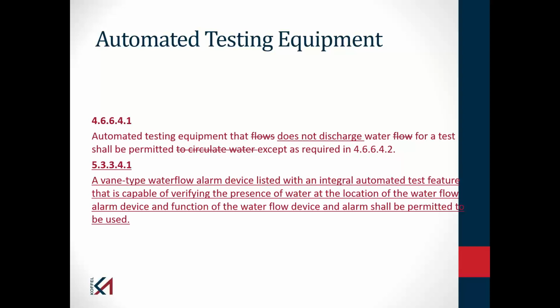So technology is advancing to the point that I can now get automated test equipment for certain components of my sprinkler system, one of which is a water flow alarm. So in the 2017 edition, we recognized that automated test water flow device, but we required it to flow water. A change in the 2020 edition will now say you can put in an automated test water flow device that does not require you to discharge water. But it does have to be able to verify that you have water in the pipe.